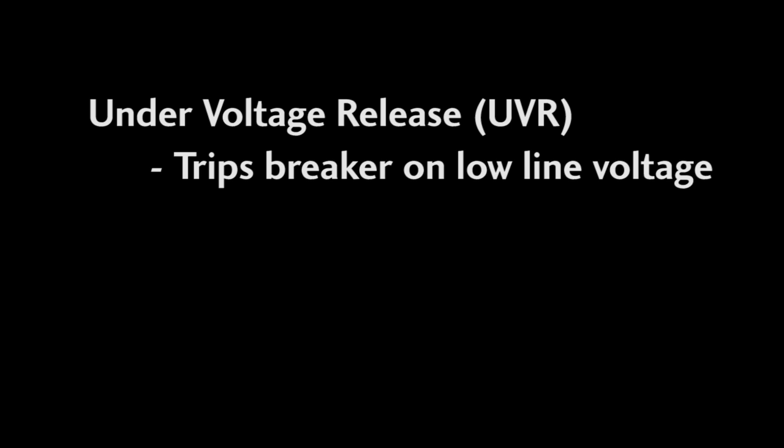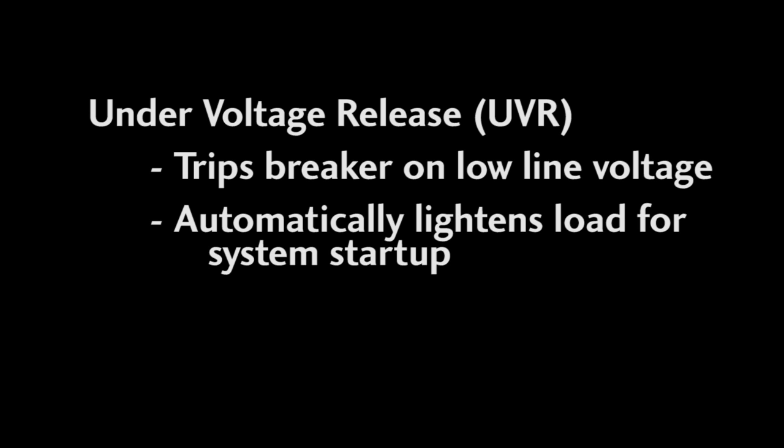An undervoltage release – or a UVR – trips the breaker when it senses line voltage is too low. This is handy when you have a system that shuts down and you want to be sure that the system isn't heavily loaded when it tries to start back up. The UVR will have tripped the breaker when the line voltage dropped so when you go to bring the system back up, this load won't be a burden.